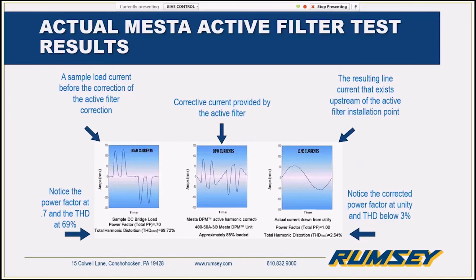So here's some actual test data from our active filters operating. As you can see here, this is a lot more severe than what you'd see out in the field, but on the left here you see a very distorted double humped bridge, like pulse width modulation, looking much like a 6-pulse drive would, except here we see upwards of 70% THD with a poor power factor.